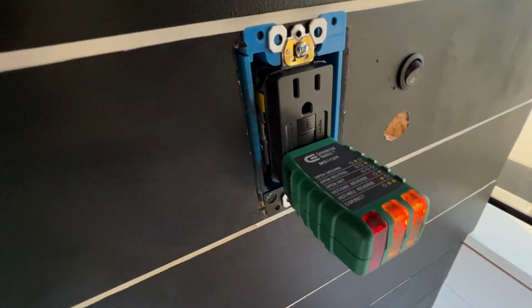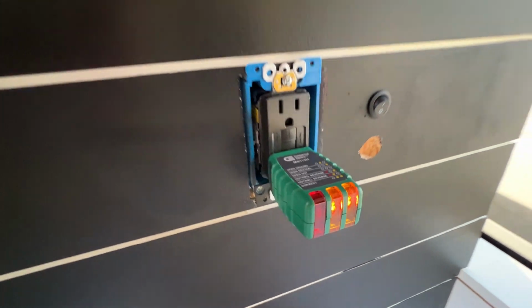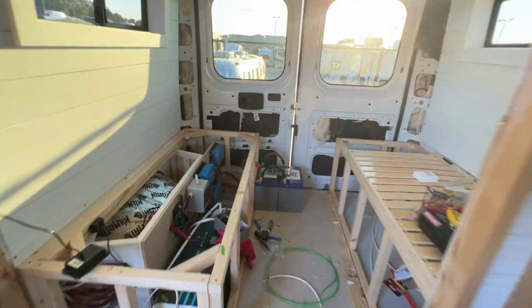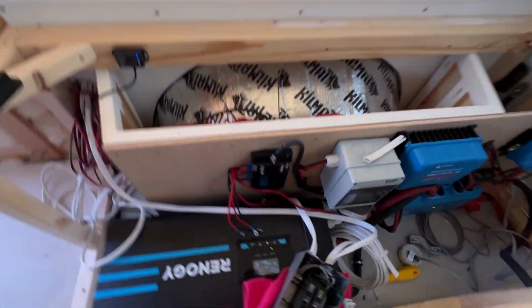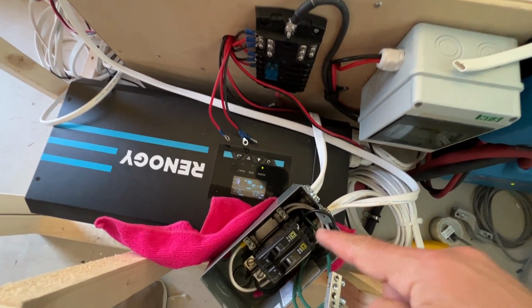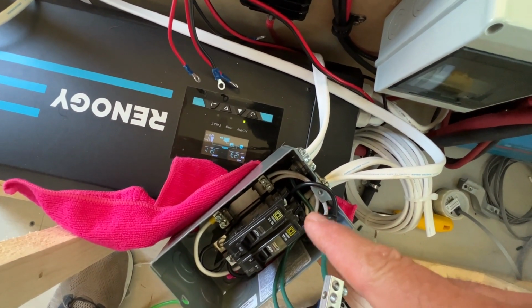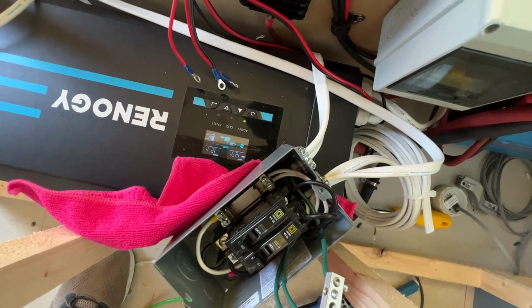So when I turned on the 20 amp circuit, which is this one, this went on and it shows correct polarity and everything. So that means those two black wires that go into the circuit breakers need to be switched. That one needs to go there and that one needs to go there.